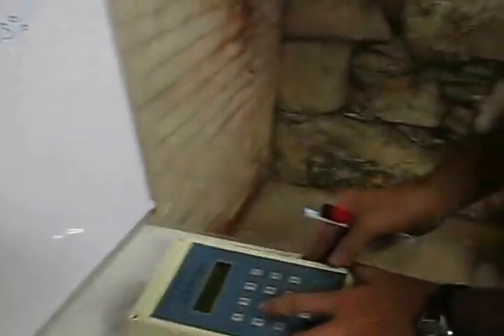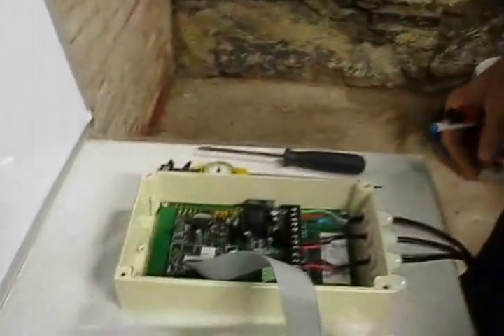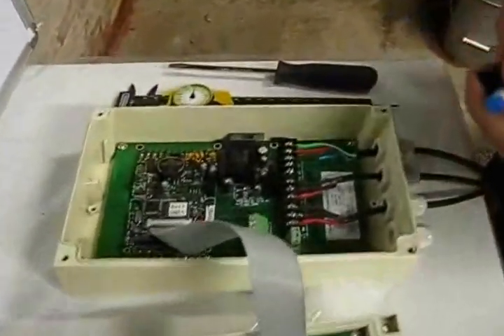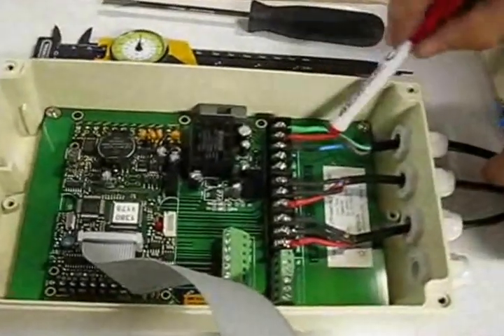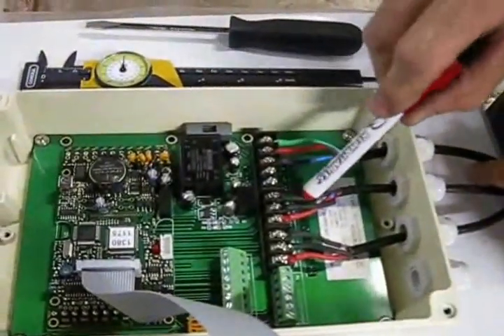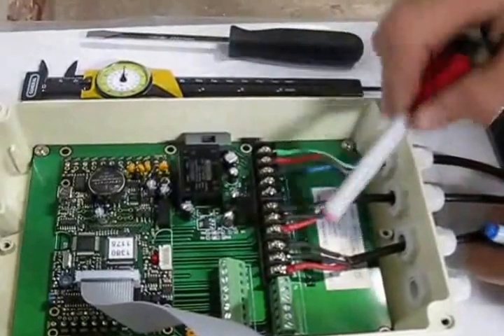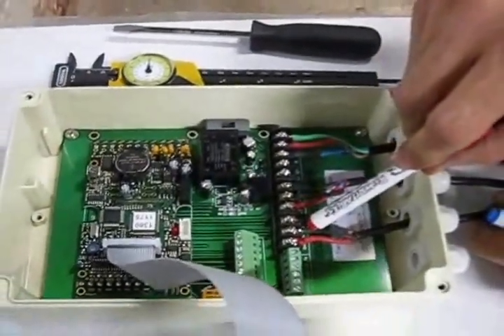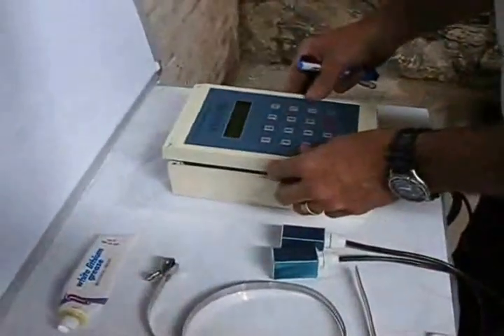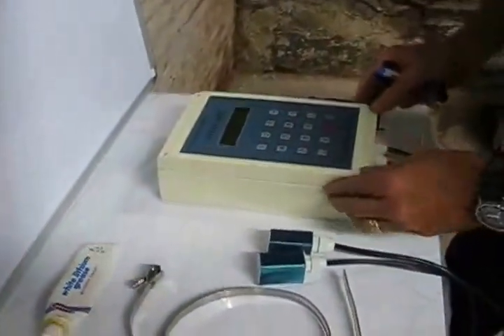The next step is to wire and power up the flow meter. Remove the 4 screws, taking care not to damage the ribbon. Here we've already wired up our transducer. We have our power coming in on the right side. The middle is the upstream for the transducer, and the left side is the downstream for the transducer. After those are wired, you replace the cover, attaching the 4 screws.